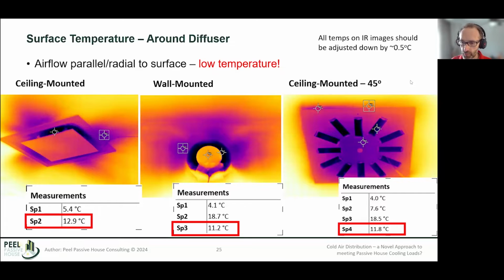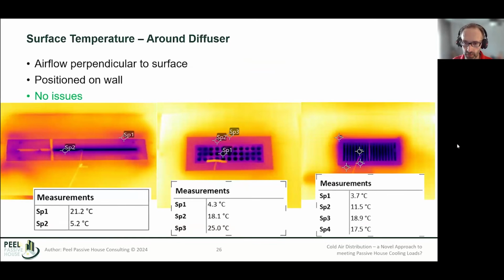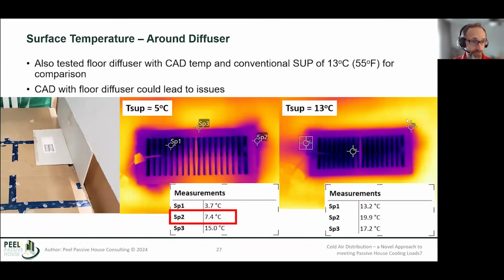Didn't have enough time to really investigate further, but certainly a questionable result there. If, on the other hand, we project the air perpendicular to the surface, so for instance on the wall, projecting it like the Coanda effect just below the ceiling, around the diffuser here, we didn't have any issues, right? You can see both thermographically, and I've also got temperature spots here well above our risk of mold growth. So provided we seal up the diffusers well and project the air horizontally, it works well, right?